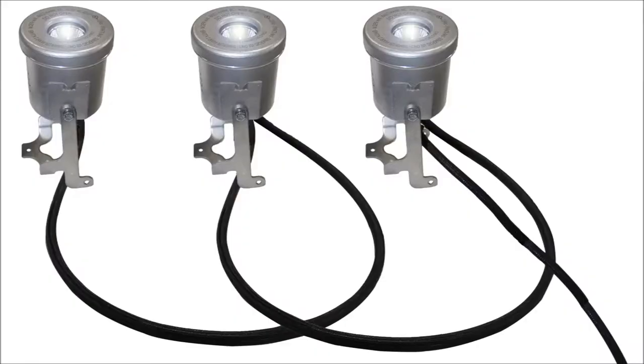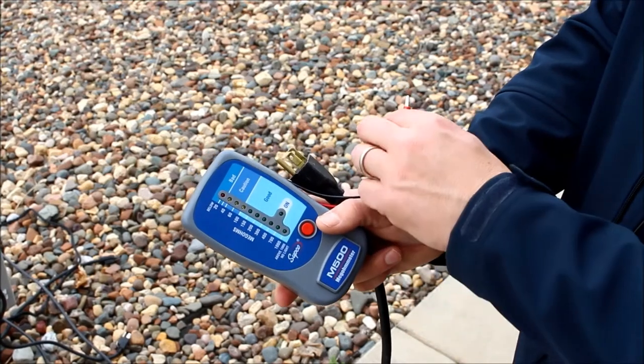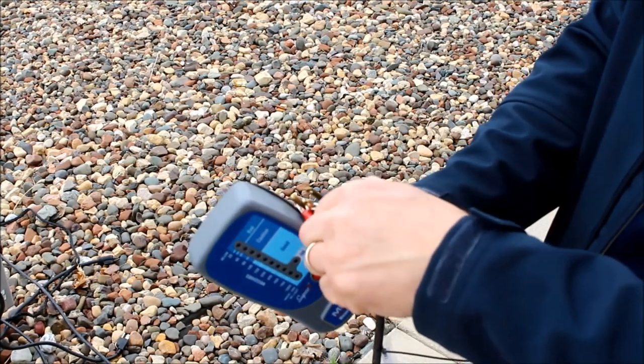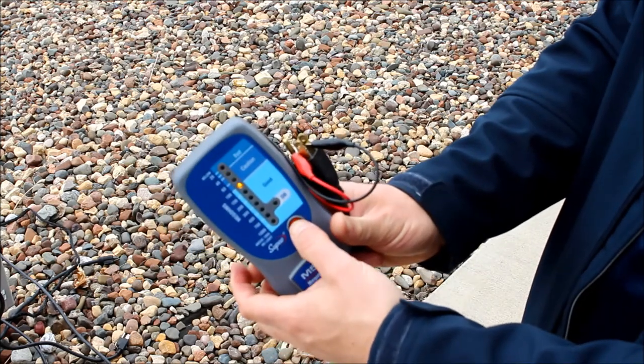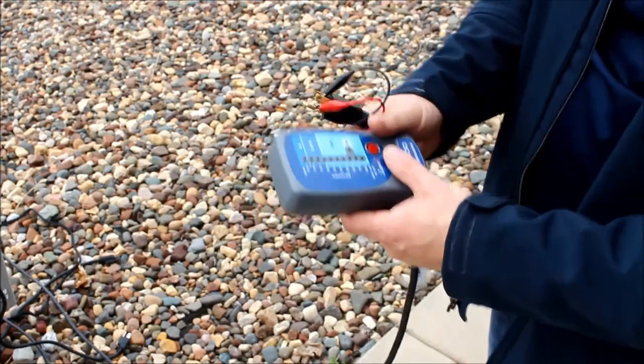If the stainless steel LED lights trip the GFCI by themselves, they should be sent to Casco for repair. If the unit is determined to be the cause of the GFCI trip, you will now need to use your megohmmeter to further diagnose the problem. With the unit unplugged, use the megohmmeter to test between hot or the black wire to ground, and neutral or the white wire to ground. To get an accurate reading, make sure the unit and power cord are still submerged in the water. If both tests read good, then the motor and the cord are good, and the problem may exist elsewhere in the circuit. If either read bad or caution, the issue is in the power cord and/or the unit.